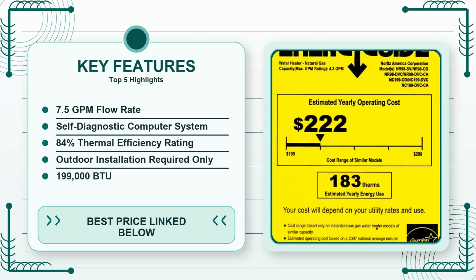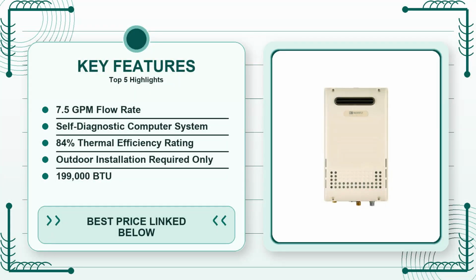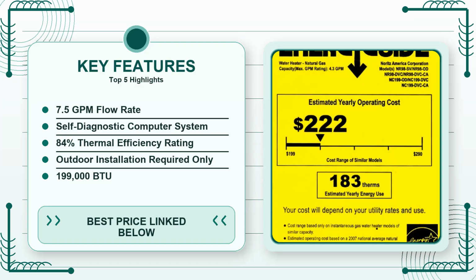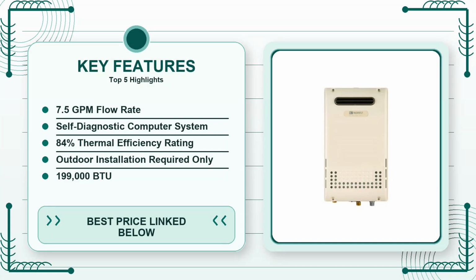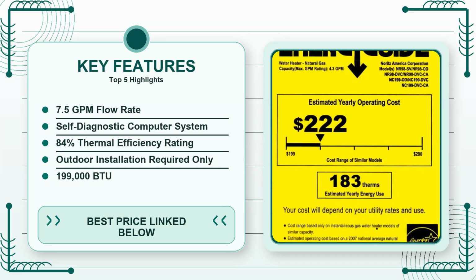Another practical advantage is the outdoor-only design itself. Because it's built to stand up to the elements, the unit's heat exchanger is coated with a corrosion-resistant finish. In areas with harsh winters, owners have reported that the heater can sit idle for weeks without any noticeable performance drop, as long as the freeze protection valve is set correctly. That means you're not constantly fighting rust or scale buildup, which are common headaches for indoor tankless units that have to cope with high humidity inside a house.